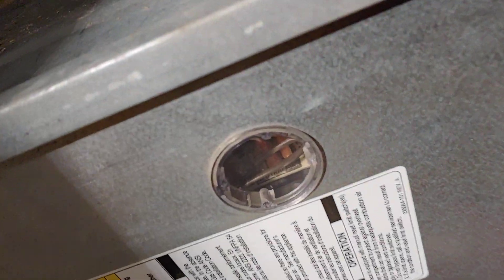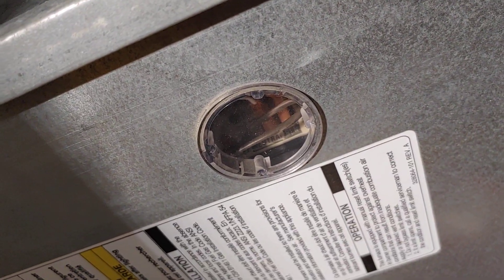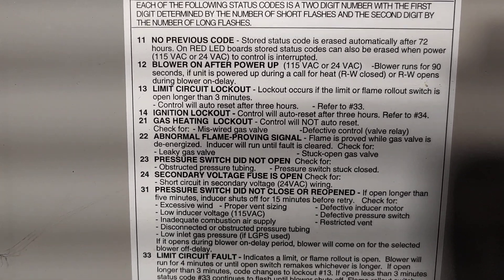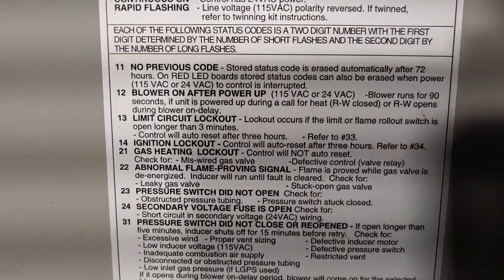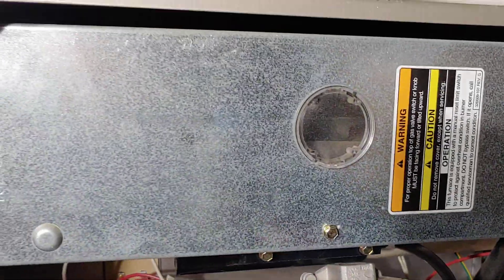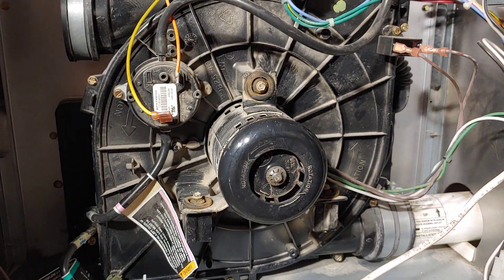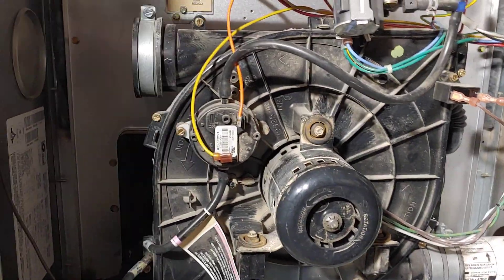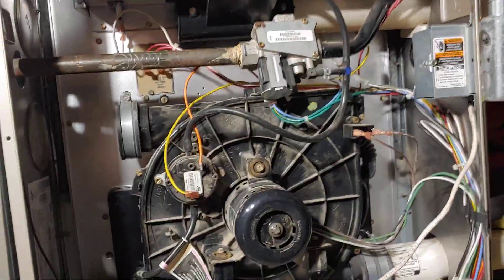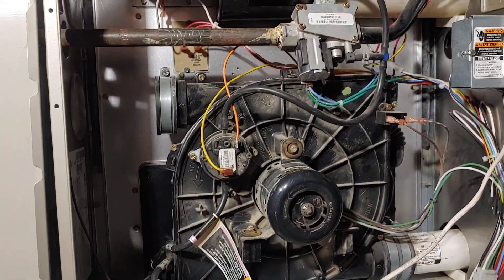Inside here is a little LED light. If this was on, it was flashing one quick light and then three long lights. On the back of your panel you always have your code — I was seeing limit circuit lockout, which just means when the blower motor is no longer functioning it has difficulty pushing the heat out, and it goes into shutdown mode. It will actually shut off for three hours, so sometimes people don't even realize what's wrong with their furnace because it just shuts off and turns back on eventually.